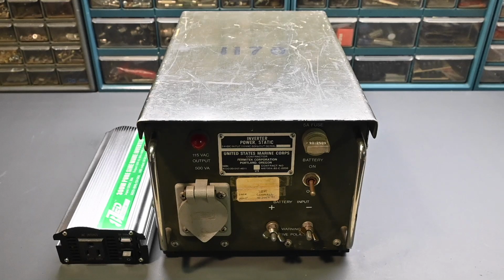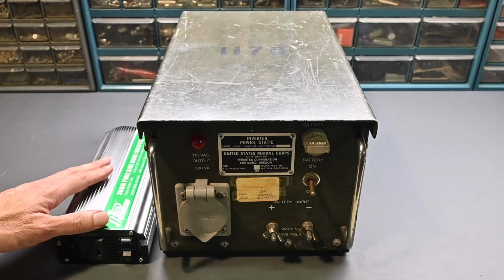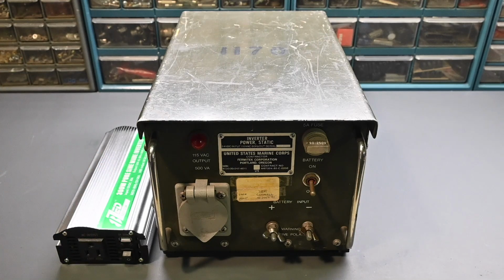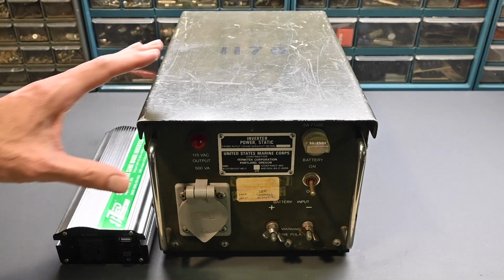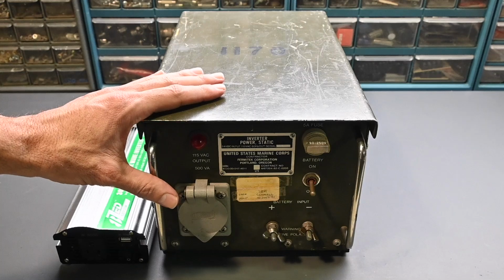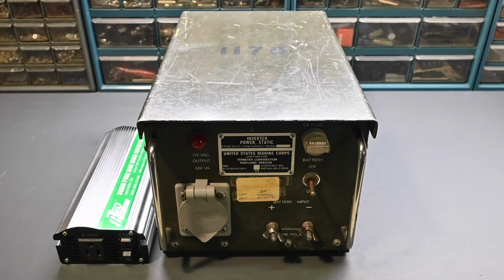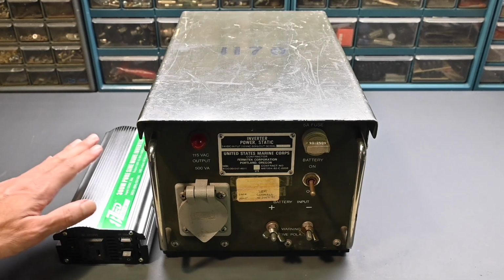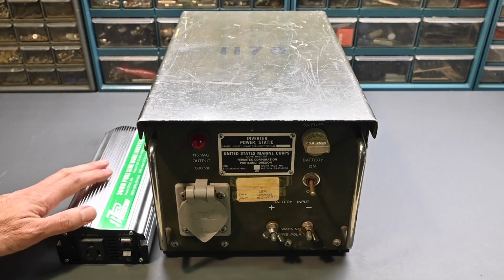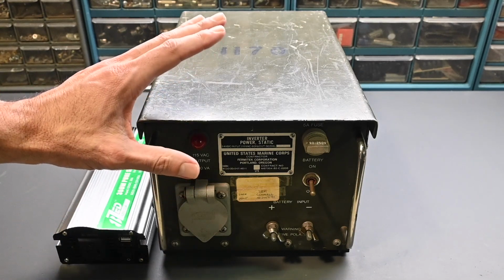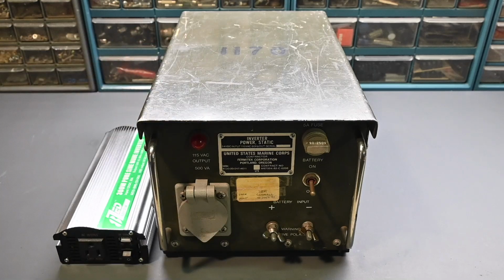Well, it has to do with the transformer that's inside the inverter. In modern inverters, the transformer is switched at a very high frequency, many tens of kilohertz or maybe even 100 kilohertz, where this inverter, just going by its physical size, must be switched at just 60 hertz. So the higher the switching frequency on the transformer, the smaller it can be manufactured. There's just less iron in the core. That allows these modern inverters to be very compact and very efficient. I'm sure this inverter is not nearly as efficient when it runs.